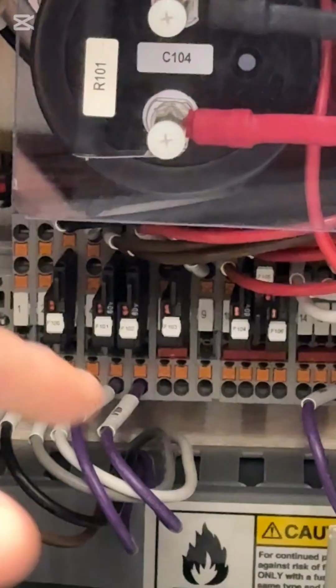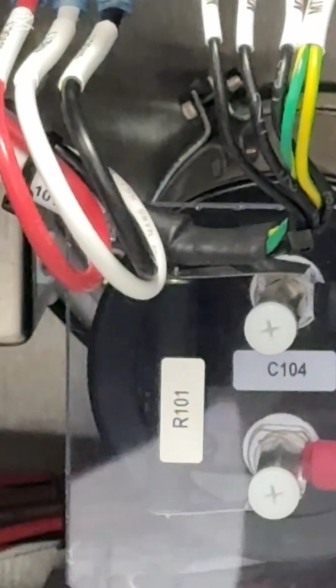Next, I'm just going to briefly go over the fuse locations in this machine. Underneath the servo chassis, you have a terminal block called TB11, and you'll see there's a set of fuses that go all the way across. You have several different voltages here, AC and DC, and they're all fused at this block going to the servo chassis. Now, if a fuse goes out, an LED may come on.